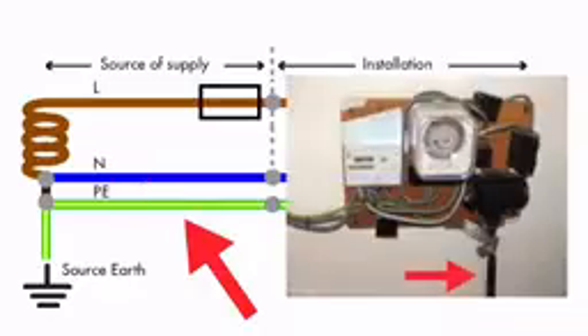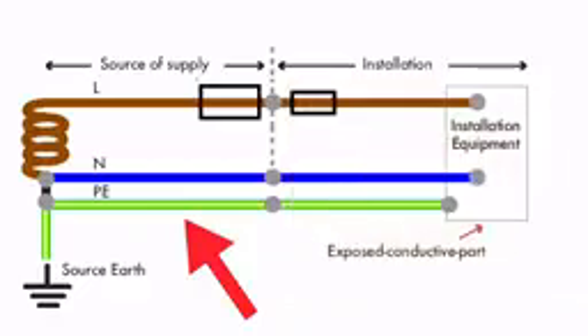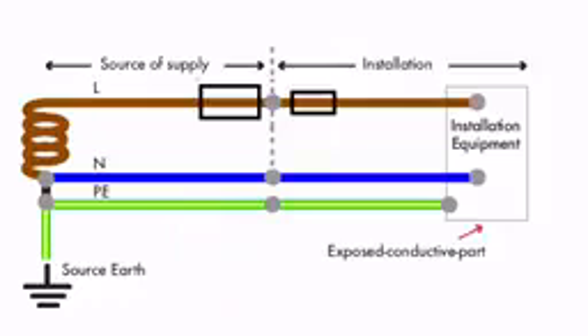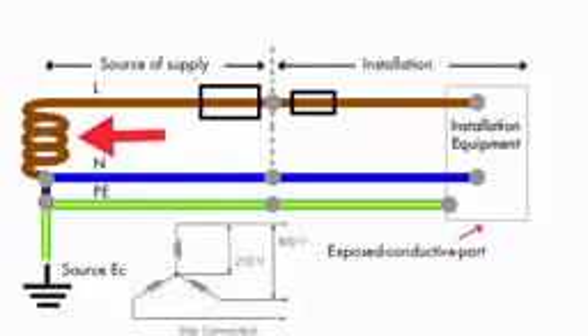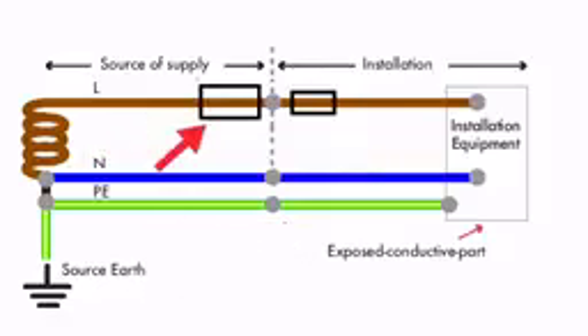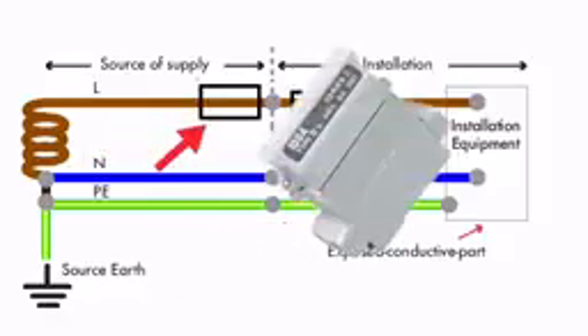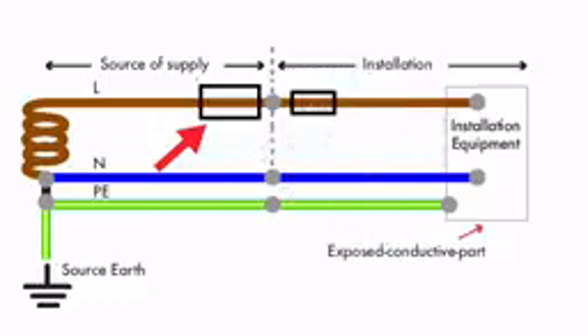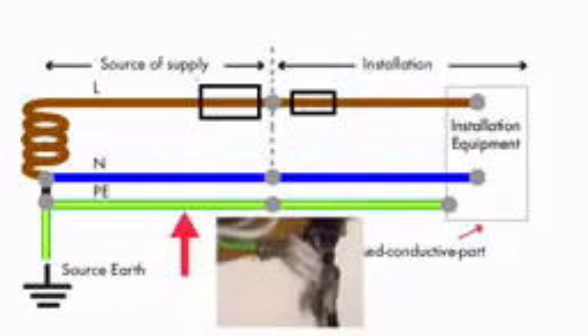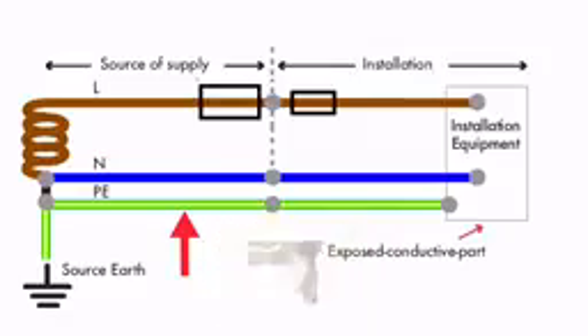This is the cable we can physically see in the bottom of the cutout. This cable often comes to installations underground but can also come overhead. This drawing also only shows one of the 3 star connected windings on the supply authority's side as well as the centre tap point to earth. The supply authorities will provide the metering equipment and the cutout fuse sized 100, 80 or 60 amps for a single phase installation. The supply authority's protective earth will be either lead or steel.